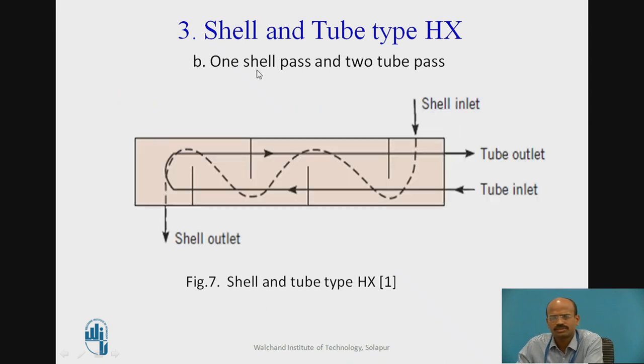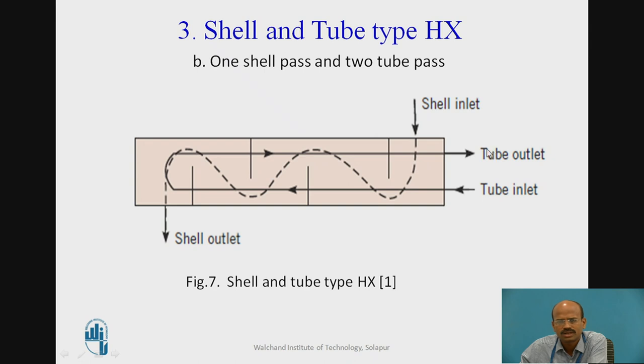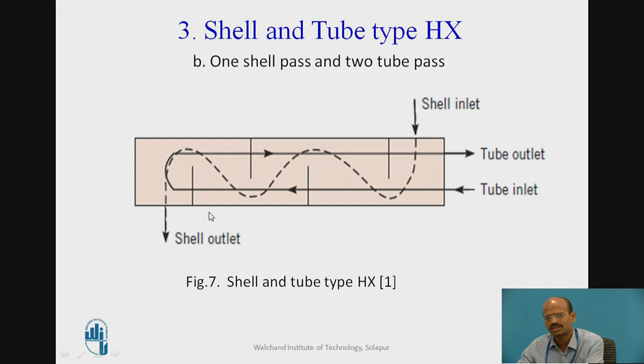In the second type of shell and tube heat exchanger, there is one shell and two tube passes. The hot fluid flows through the first pass, is then redirected and kept inside the same shell for the second pass — that is why it is called one shell and two tube passes. The cold fluid is given multiple passes using baffles, while the shell remains one.